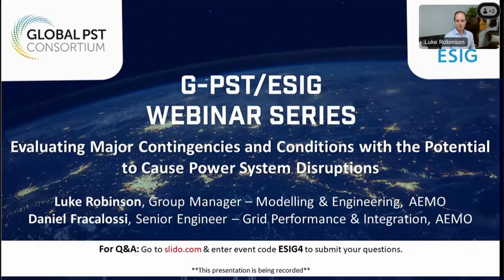But we're also looking at having synchronous condensers, potentially converting existing generation to synchronous condensers, and other sort of measures to ensure that we have the system strength and inertia in the system that we can still operate it to handle non-credible contingencies. But I think definitely the fast response that BESS can provide is going to be quite useful in the system. And so as long as it's considered properly, then this can be very helpful for special protection schemes and these sort of considerations.